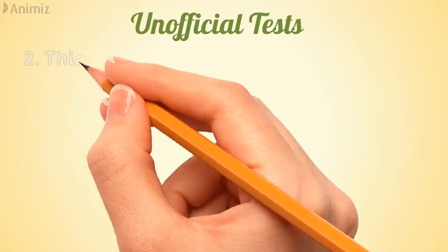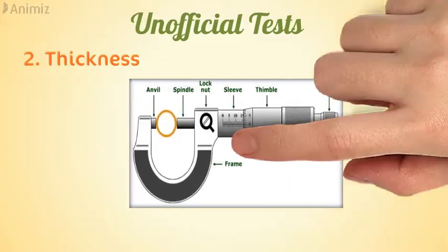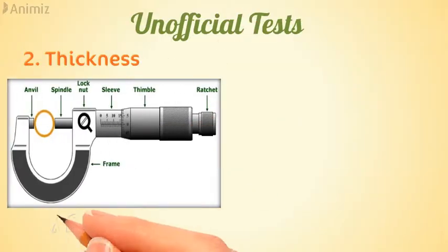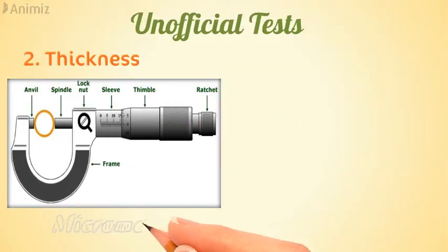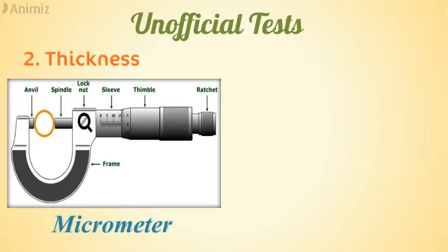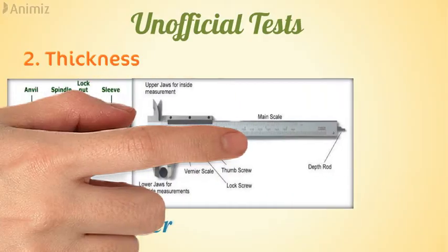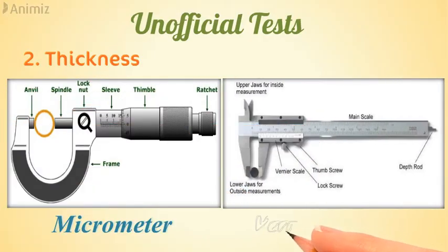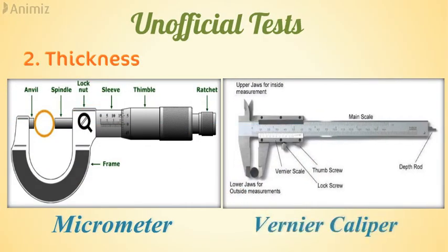The second test is the thickness of the tablet. It can be measured by a micrometer by placing the tablet diametrically between the anvil and the spindle, with thickness measured in millimeters. Alternatively, a vernier caliper can be used, where the tablet is placed diametrically between the jaws and thickness is measured in centimeters.